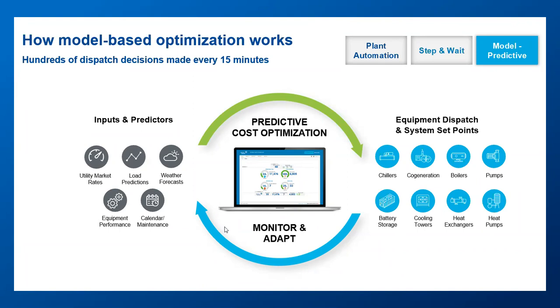This math-based approach tends to be a lot more flexible. Some of the older approaches, like step-and-wait or custom sequences, would only apply to the most common plant configurations, but tend to get tripped up with unique configurations like a sidecar arrangement, a heat pump chiller, or a glycol loop for part of the system. In my experience, every central utility plant tends to be a snowflake—they're all a little different—so this math-based approach allows much more flexibility to apply optimization methods to a lot more plants out there.